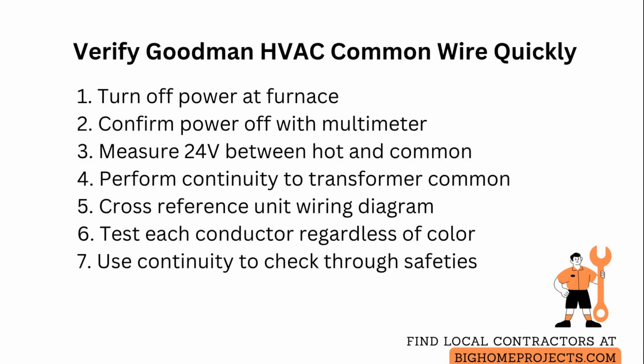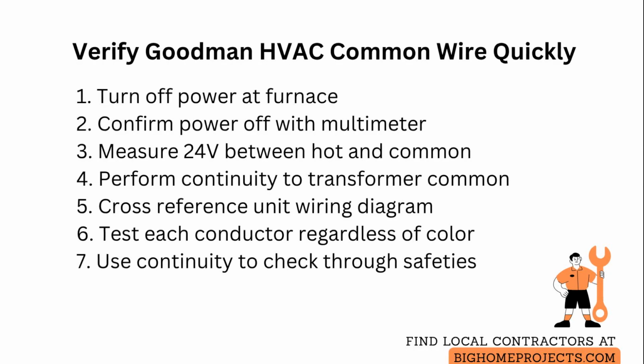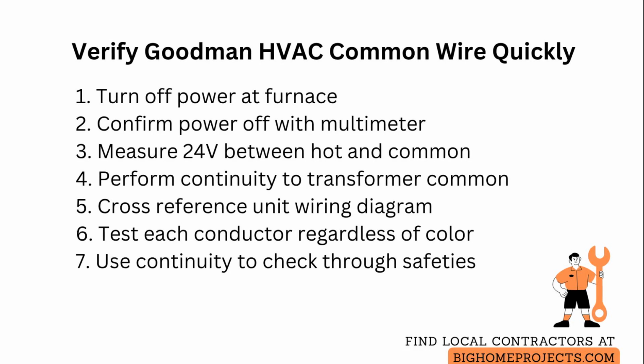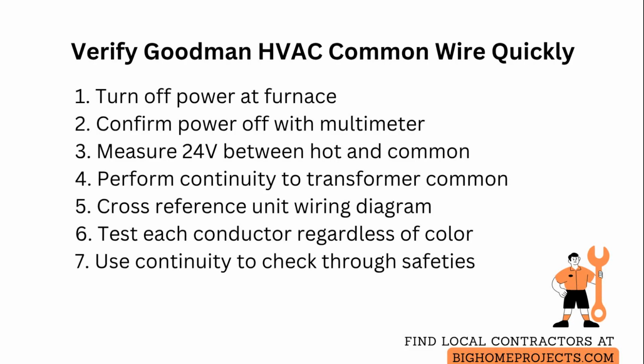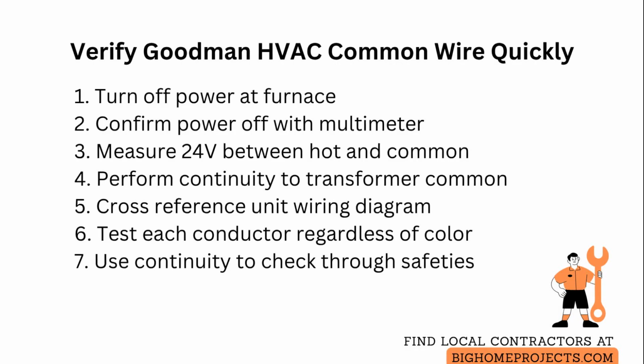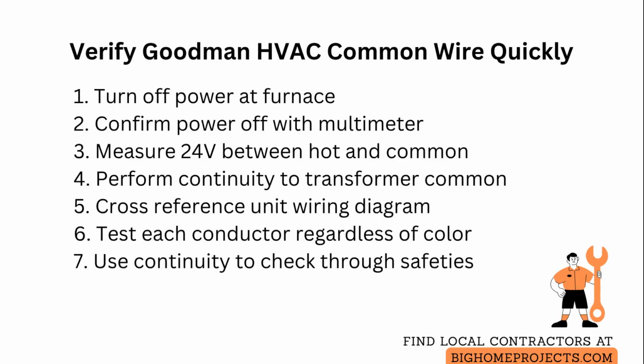the thermostat. With the system powered back on briefly and the thermostat calling for cooling, measure 24 volts between the hot lead and the suspected common. A stable 24-volt reading indicates a proper common. If you can remove the wire from the control board terminal, perform a continuity test back to the transformer common terminal to confirm an unbroken conductor.